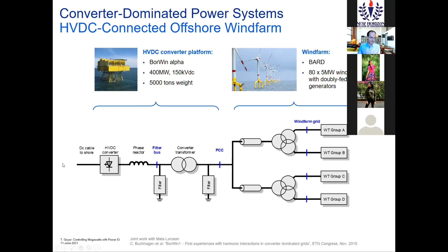Now what happened is that as more and more of these wind turbines were commissioned, large voltage harmonics started to occur at certain operating points at the point of common coupling. We're talking about more than 100 kilovolt AC with a voltage THD exceeding 20%. That's crazy. As a result, this filter bank experienced large harmonic currents, huge overloads, and damage. The question was, what happened?